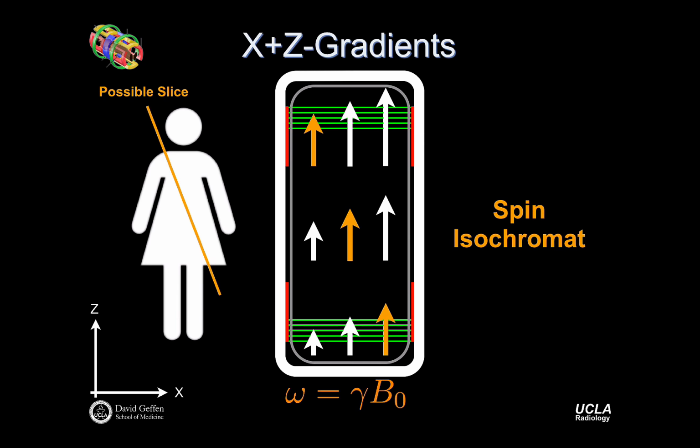So let's say my externally applied field is B0. Then in this case, I've added some gradients. So my RF pulse to excite this slice has to match B0. So it's just gamma B0, right? If I tune my RF pulse frequency away from gamma B0, which we usually just call omega 0, I can make it slightly higher in frequency or slightly lower in frequency, and I'll just be moving to excite a different parallel plane. So I can tune that RF pulse, what we call the center frequency of the RF pulse. That's one way that we steer around the imaging plane in MR.